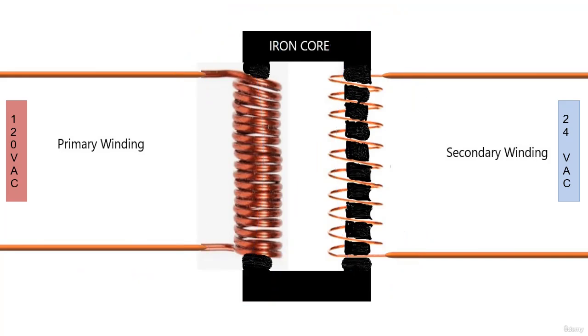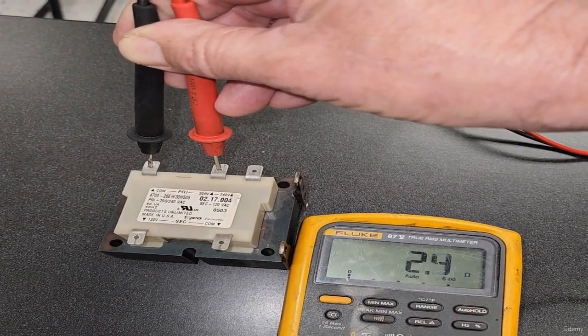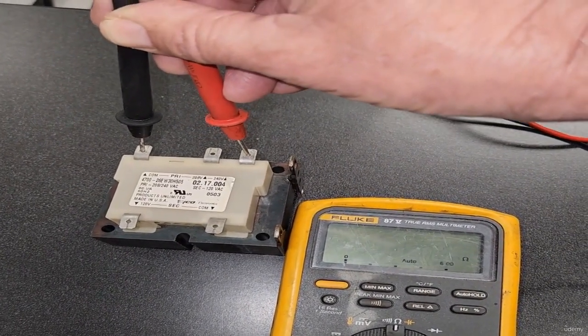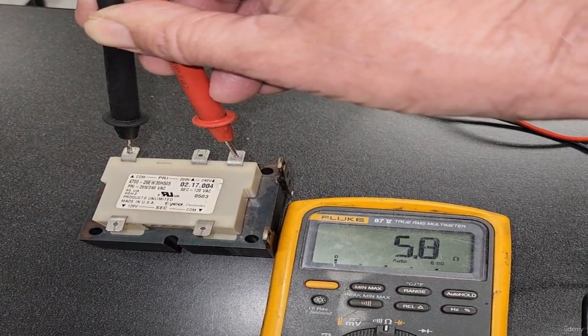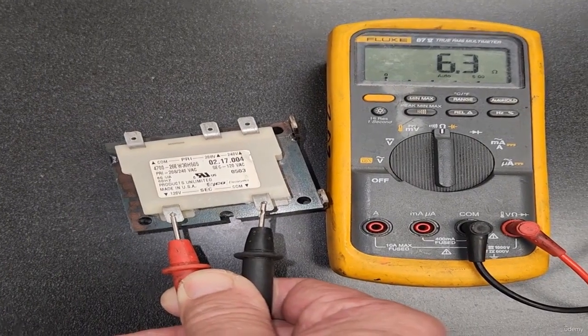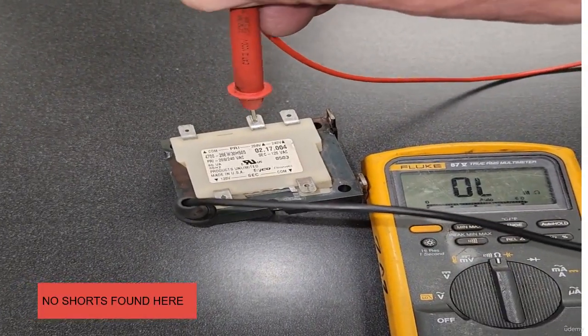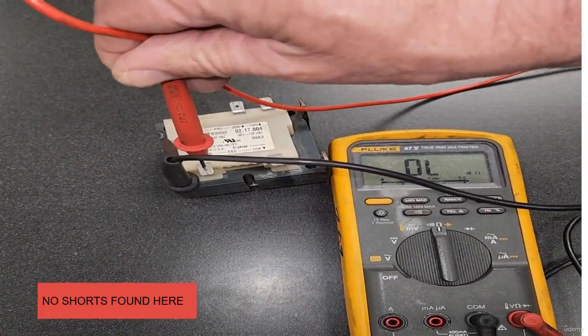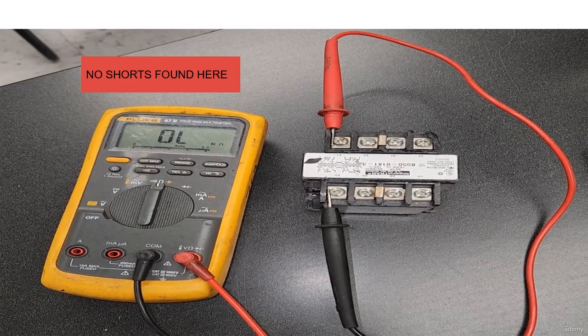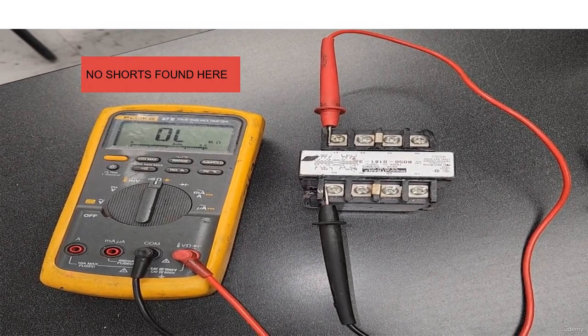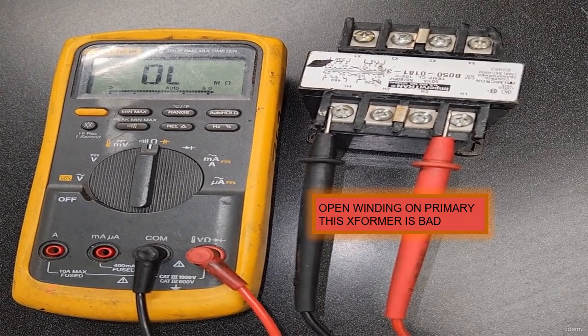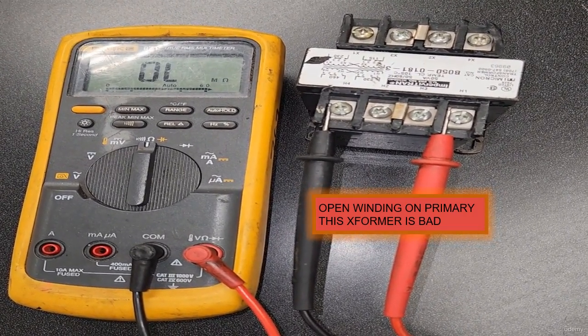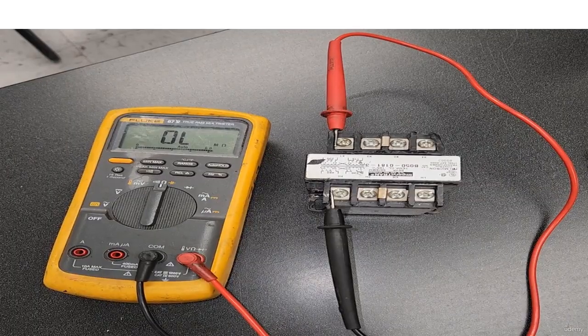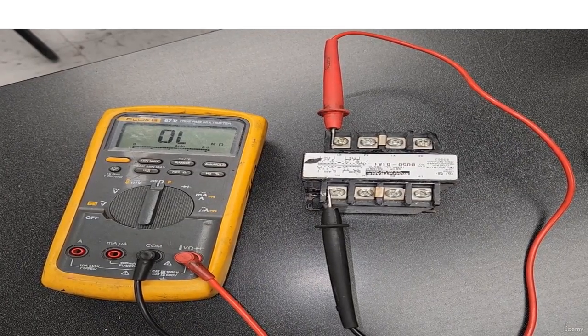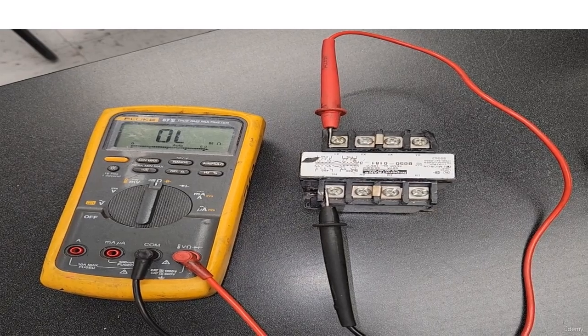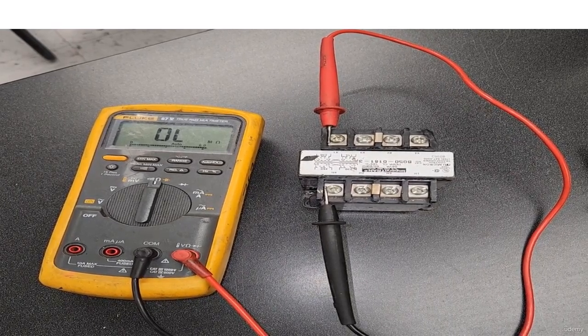the voltage fluctuation. To test one, with your meter on the ohm scale, you simply look for continuity in an individual winding. If you read any continuity to ground or its core, you have a shorted coil. If you read any continuity from the primary to the secondary, you have a shorted coil. If you read infinite on an individual winding, the coil is open and bad. The primary and secondary do not electrically touch each other, so you should read infinite or open line if you read the primary to the secondary.